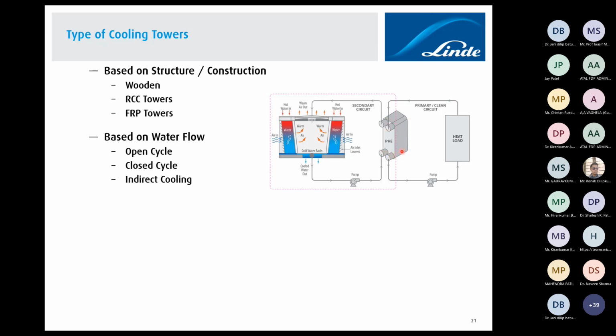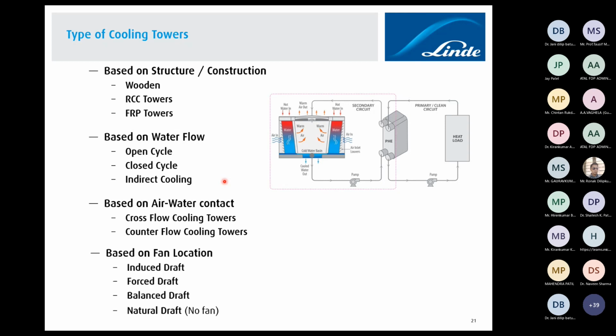So this is how you can have a small number of heat exchangers with superior metallurgy and the large majority of exchangers with carbon steel. So you will get a very good cost advantage by doing this kind of indirect cooling. Based on air-water contact, yes, Jay Patel rightly said, cross flow or counter flow, depending on how air is moving inside the cooling tower. And based on the fan location, yes, that was also touched upon, like natural draft, where no fan is needed, no mechanical energy is needed, and because of the parabolic nature of the cell or tower, that creates the draft from bottom to top, and that takes away heat from the circulating cooling tower water inside the tower.